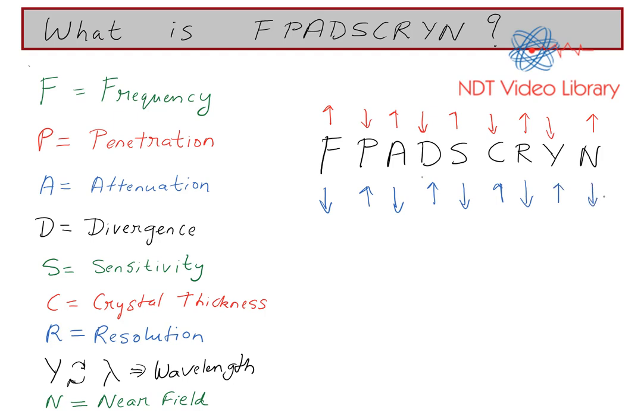Now let's see how we can use this. Consider frequency going up. If I increase my frequency, then the penetration goes lower — so I don't get more depth of penetration, I get more attenuation — and so on and so forth: crystal thickness goes down, resolution goes up. You can find the relationship between any two parameters.